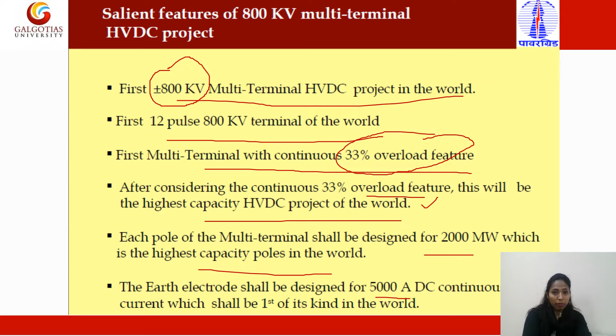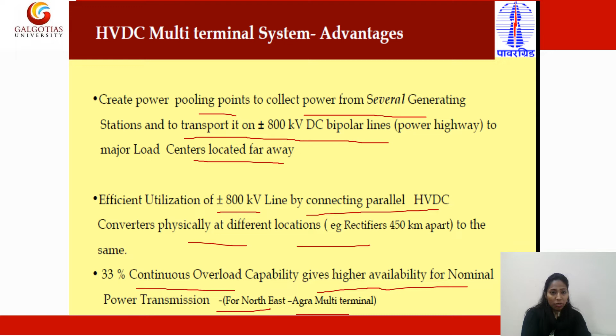Now, what are the advantages of multi-terminal HVDC? It creates power pooling points to collect power from several generating stations and transport it over plus minus 800 kV DC bipolar lines. We have the option to interconnect multiple systems through the HVDC line, a power highway to transmit power to major load centers located far away. It gives efficient utilization of the plus minus 800 kV line by connecting parallel HVDC converters physically at different locations. The 33% continuous overload capability gives higher availability for nominal power transmission for the Northeast Agra multi-terminal stations.